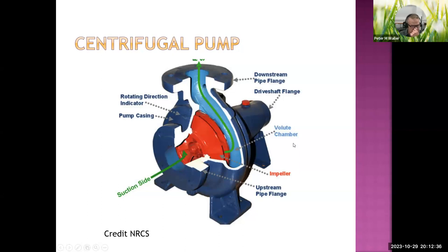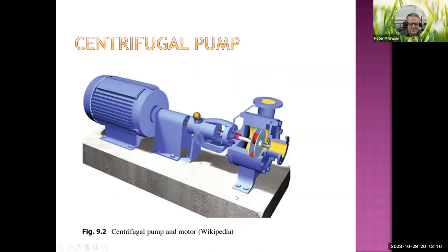A centrifugal pump is the opposite of an axial flow pump. In a centrifugal pump, suction enters at the end and the direction of the water is turned — it's thrown outward toward the volute casing, which adds pressure. The water then exits sideways from the direction it came in. The motor drives the impeller, which throws water toward the outer volute, and then it exits through the discharge.